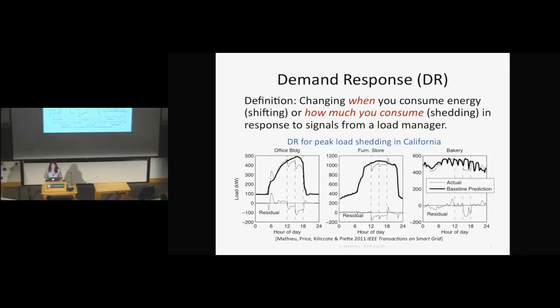This demand response program is for peak load shedding. When the system in California is reaching its peak, there's not much capacity left because everyone's using power. It's a hot summer day, and we don't have any more power plants to bring online. Power becomes very expensive, and the system starts nearing its thermal limits and might collapse. You might have a power outage.